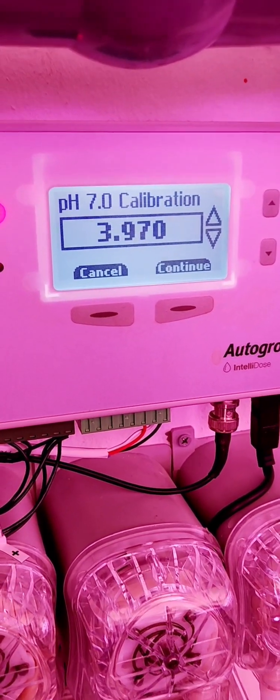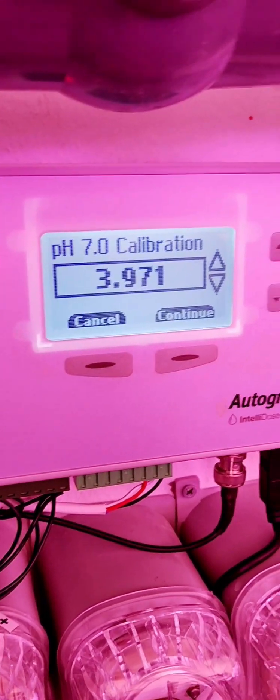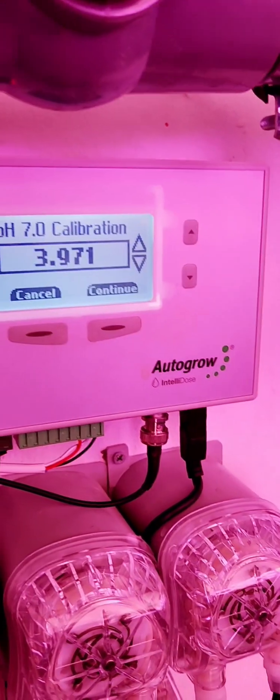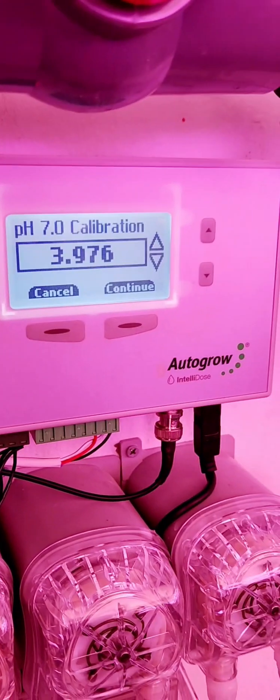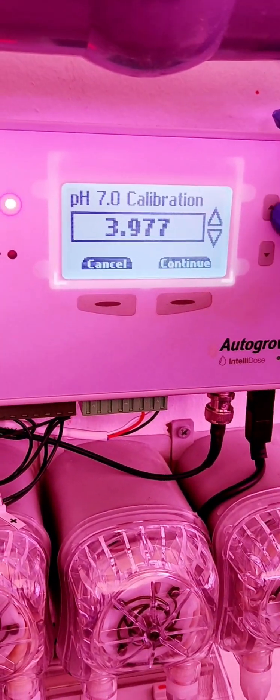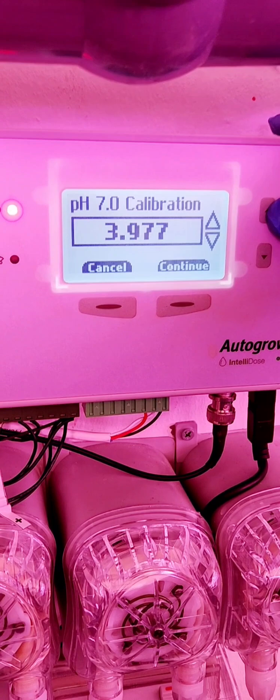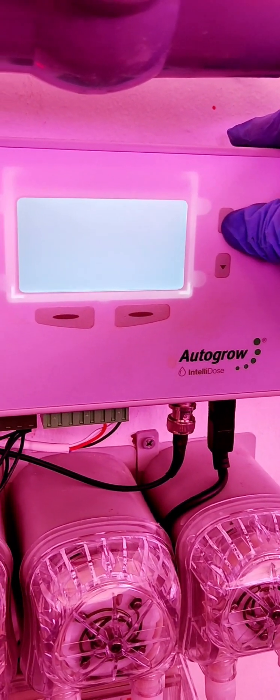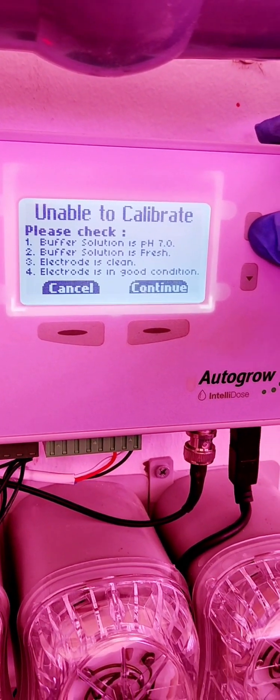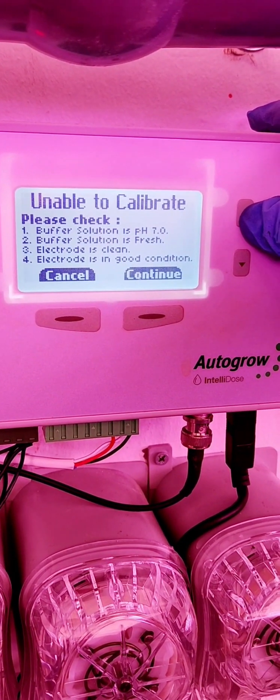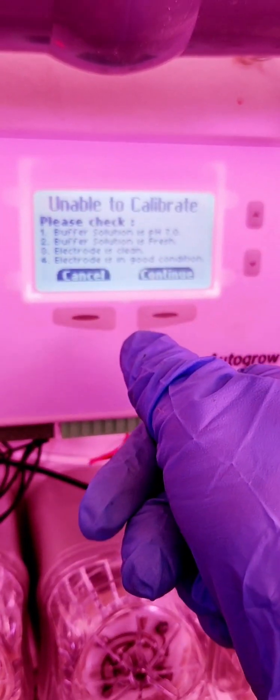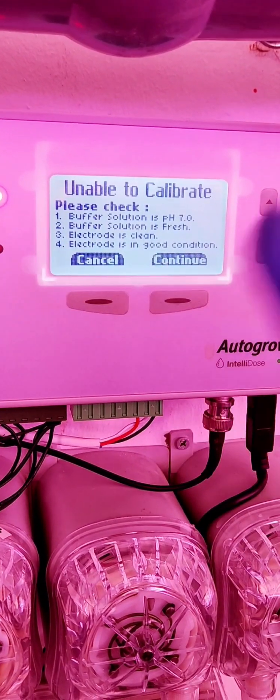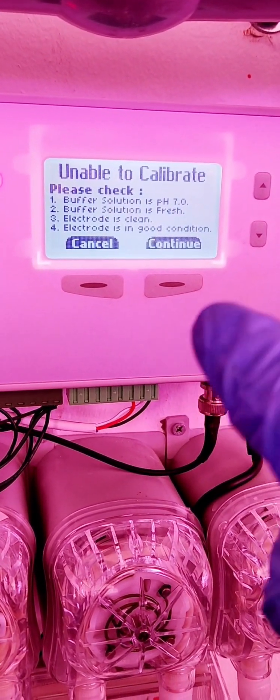But, in this case. In this one machine. I noticed the pH probe is not really functioning. If I will try to adjust it. I want to increase the number to achieve the 7.0. There. Unable to calibrate. Meaning to say. It's giving. The system is giving some tips. How to check or to consider why we cannot able to calibrate.